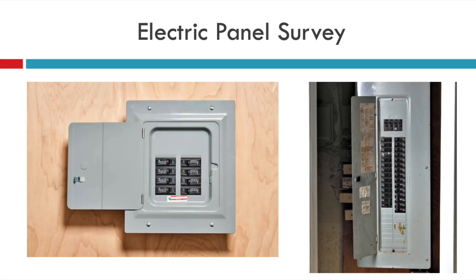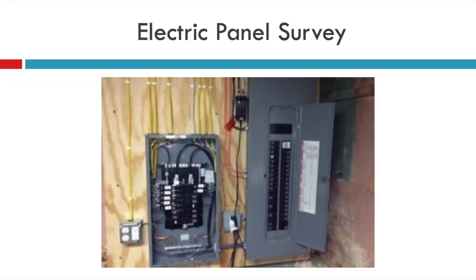Just because you have a panel this size does not mean it was done correctly — it should match the service wire going to it. If the electrician or the homeowner pulled an electrical permit, I'm willing to bet that's actually the case, but you want to verify. At my house, I actually have a 200-amp circuit wire running to a 100-amp panel, because when I bought my house the wire was damaged and I knew I was going to do an upgrade. I had the electrician run the larger wire to handle a bigger service when I could afford the panel change. Also, just because you have a 100-amp panel doesn't mean there aren't sub-panels — they're often located right next to the main panel. If you have PV panels on the roof, you might have multiple sub-panels. Keep in mind, there should be no more than six disconnects to shut off all the power to the house — that is in the code.